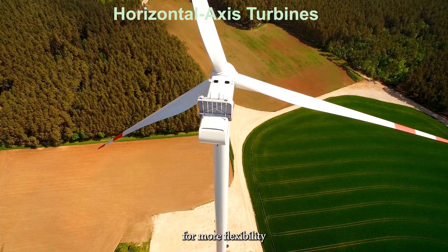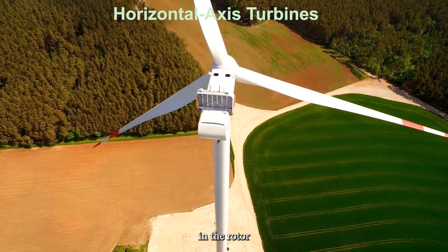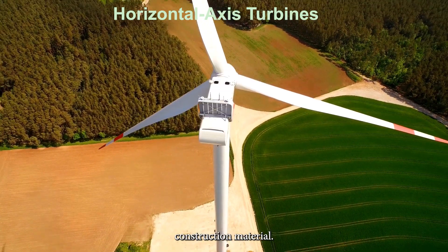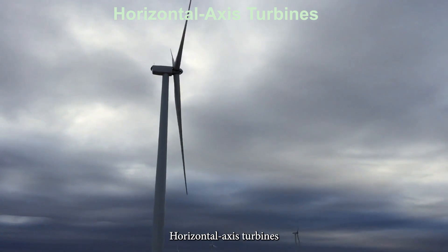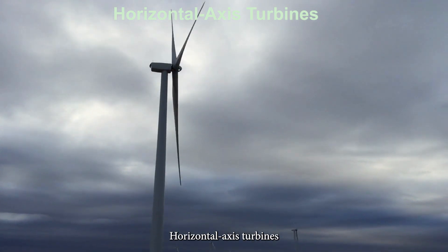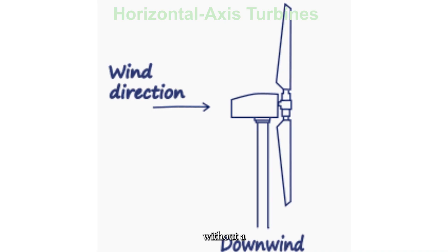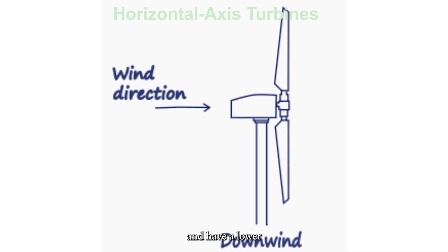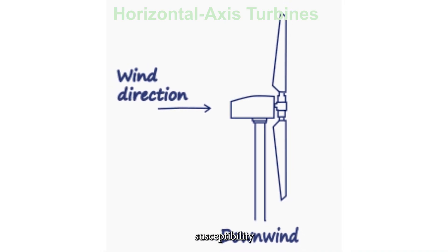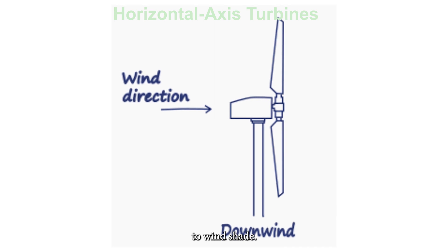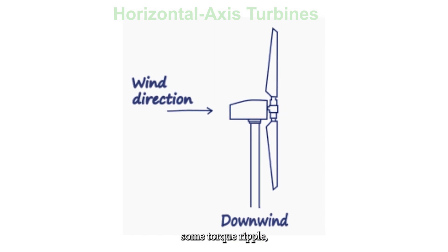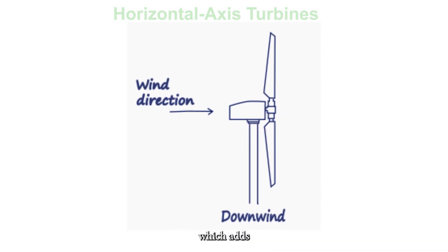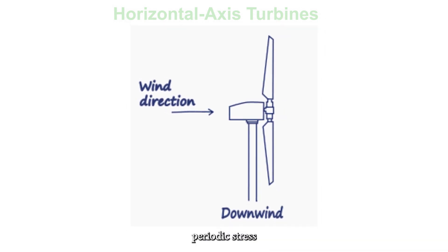This design allows for more flexibility in the rotor blades and lighter construction material. Downwind horizontal axis turbines can operate without a yawing mechanism and have a lower susceptibility to wind shade. However, they do experience some torque ripple, which adds periodic stress to the turbine structure.